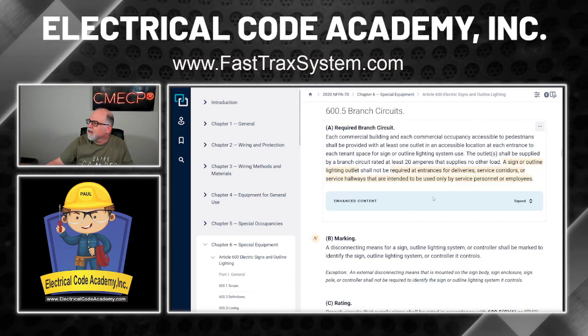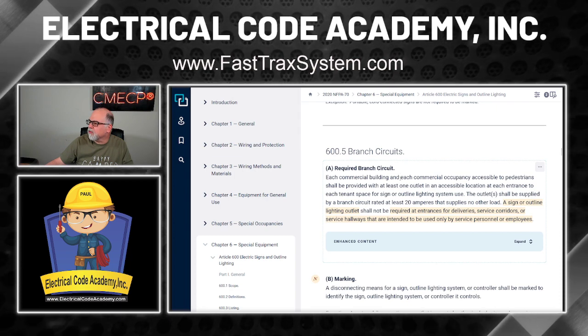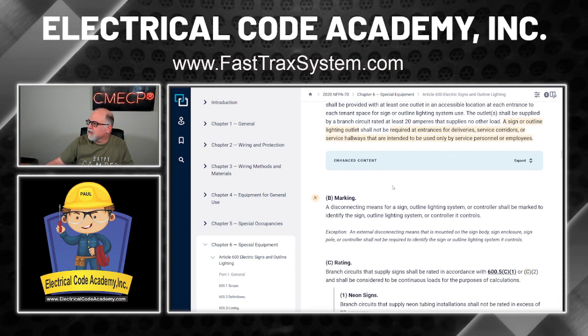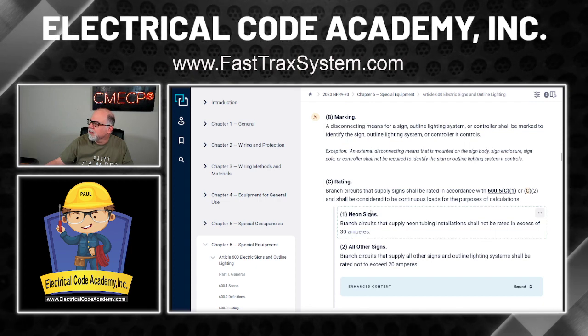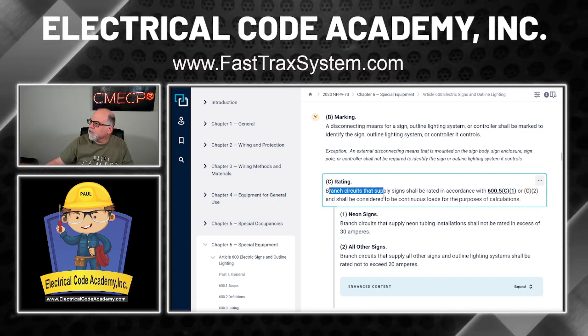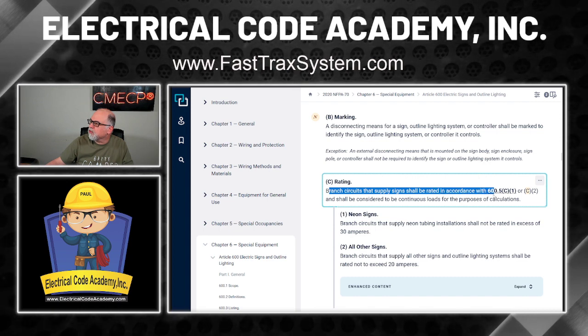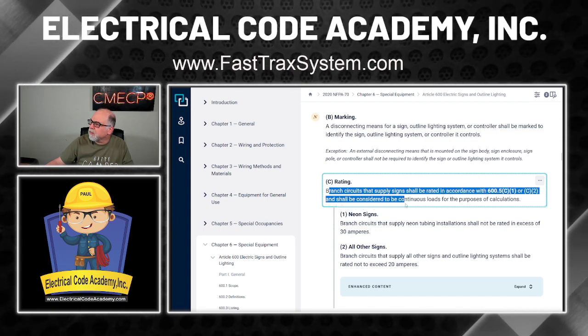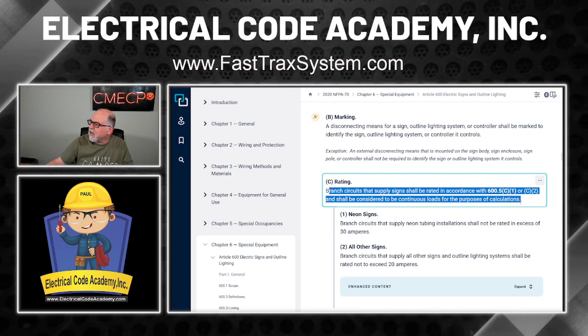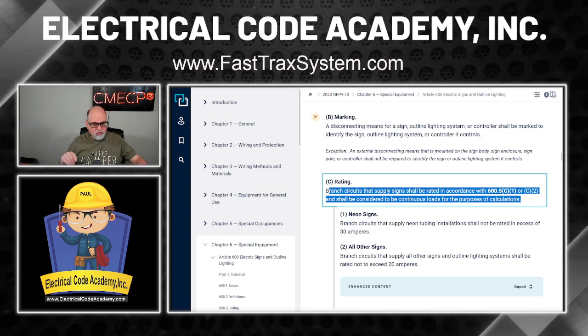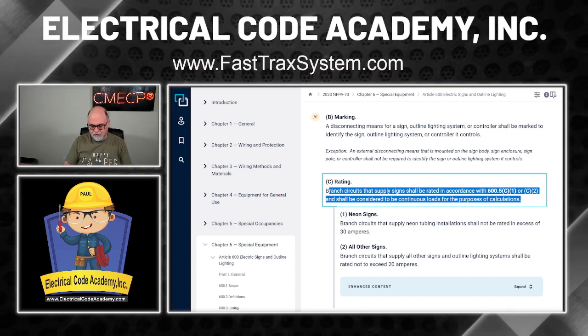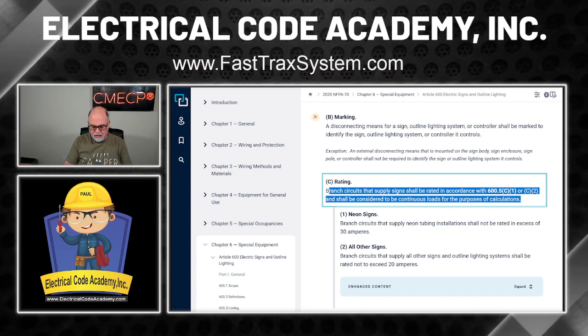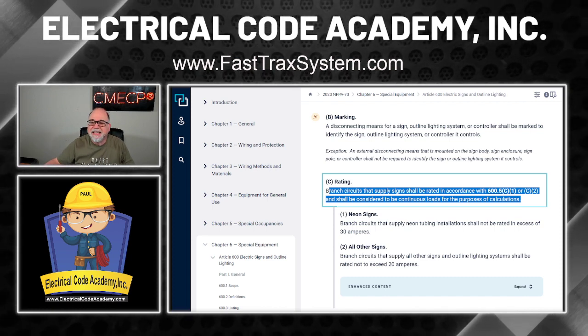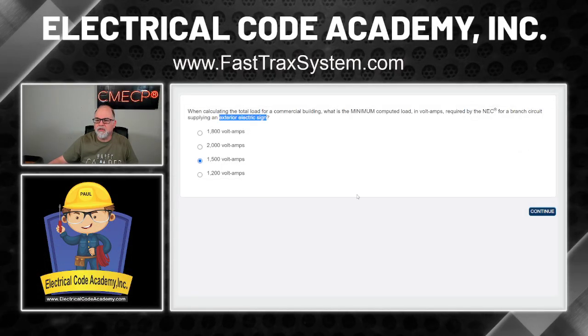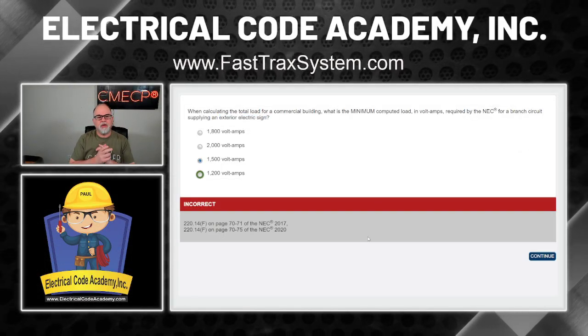Branch circuit rating. All right, here's the branch circuit requirements right here. And let's see here. Now, notice, branch circuits that supply signs shall be rated in accordance with 600.5(C)(1) or (C)(2) and shall be considered to be a continuous load for the purpose of calculations. So, if that's the case, let's take a chance here. So it's 1200 times 1.25. That is 1500. And let's go back and look at our question.